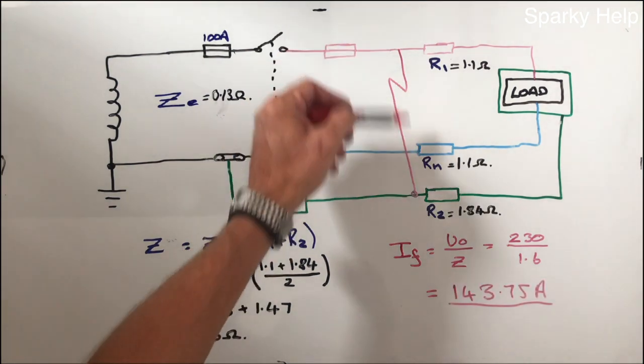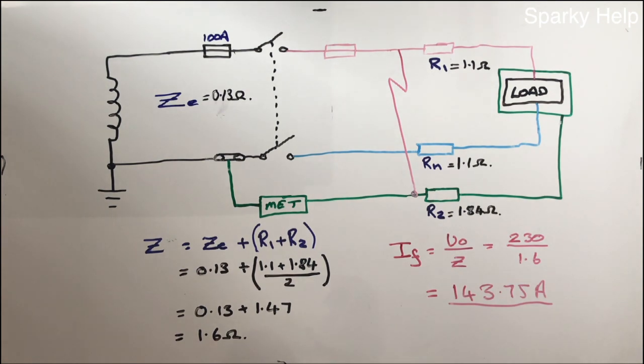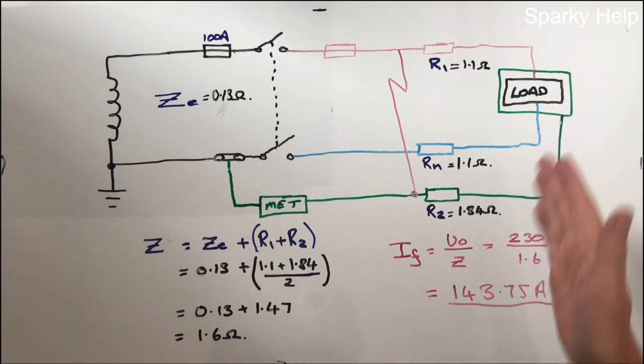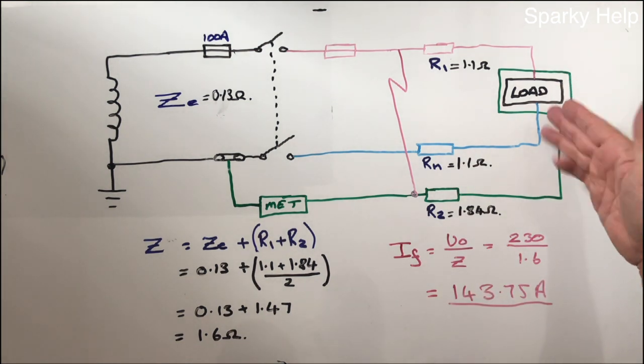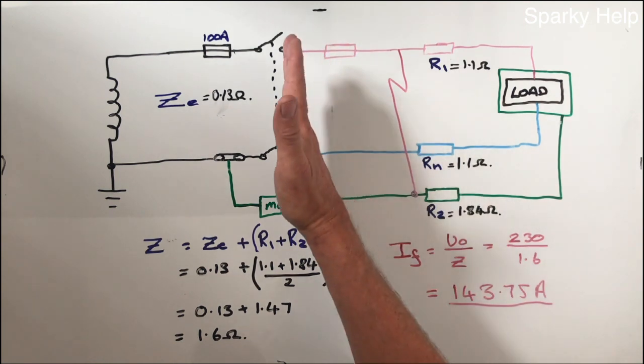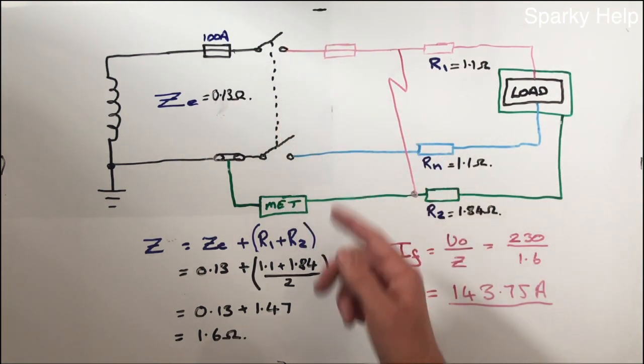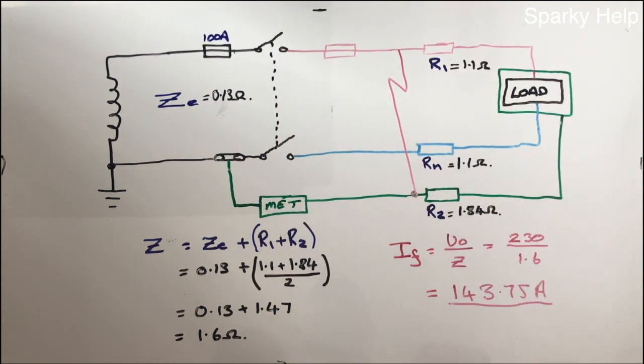So the fault current that would flow in this location would be 143.75 amps. What you probably realise then is that, obviously the reason we do ZS is because it's the worst case scenario of that circuit, it's the lowest fault current in the circuit. Any fault that is closer to the origin of the supply, the fault current is going to go up, and therefore quicker disconnection of that protective device.